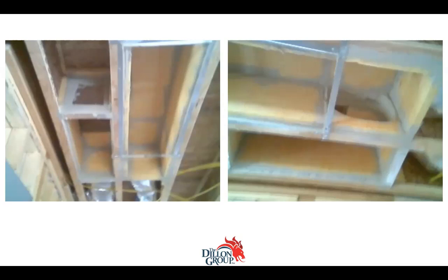However, you can get your HVAC contractors to at least meet you in the middle. Hey, let me get a return in every bedroom at least, as well as the main one in the hallway. And, oh, no, we'll use the door undercuts. Well, if you look in Manual D, for instance, a master bedroom with a decent sized master closet and master bathroom, you might need 300 CFM to that area. Your door undercut per Manual D for 300 CFM is 4.7 inches. Who wants 5 inches cut off their master bedroom door?